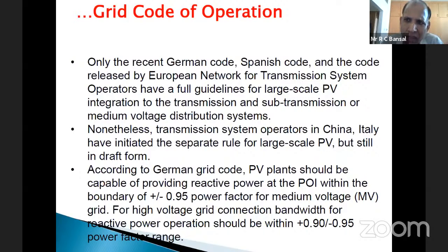But for the large scale PV system, as you can see in the last bullet point, for example, according to the German code, PV plants should be capable of providing reactive power at the point of interconnection within the boundary of plus minus 0.95 power factor. What does it mean? It means that these PV plants will not operate at unity power factor, but in leading or lagging power factor mode. The PV plant can supply or absorb reactive power depending upon the requirement.